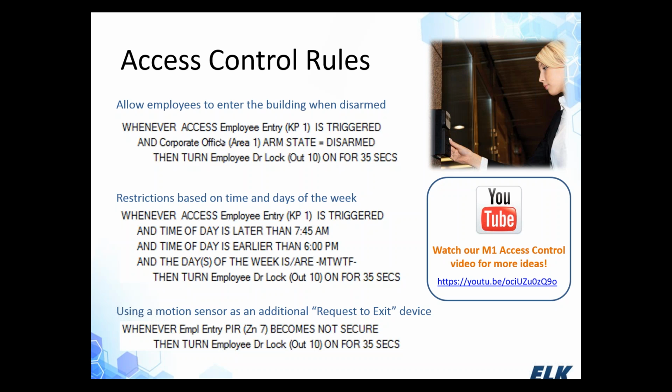You could also incorporate another and statement like we've done here at the bottom, where you can say the time is later than 7:45 a.m. and the time is earlier than 6 p.m. and the days of the week are Monday through Friday. Then let this employee in. So this employee, or anyone with access as their user authorization, only has access to this area from 7:45 to 6 p.m. Monday through Friday.